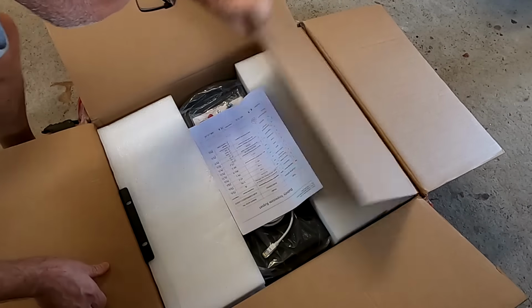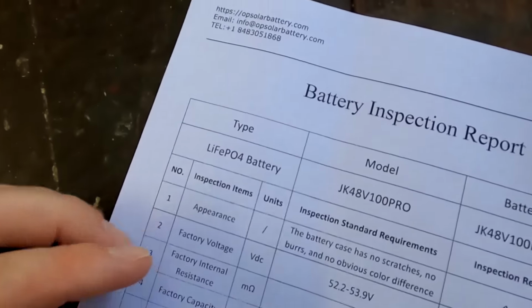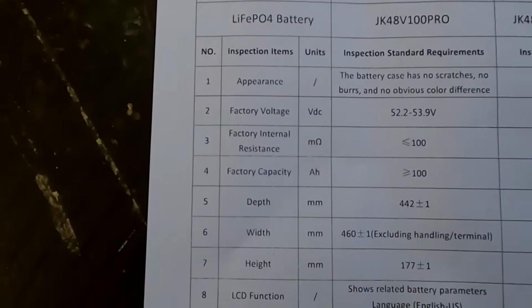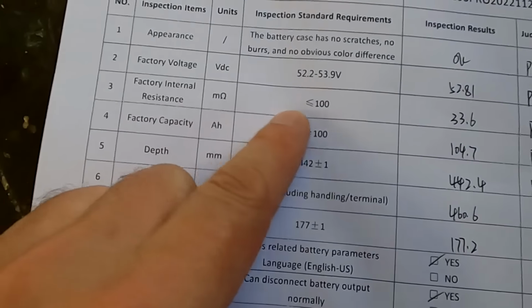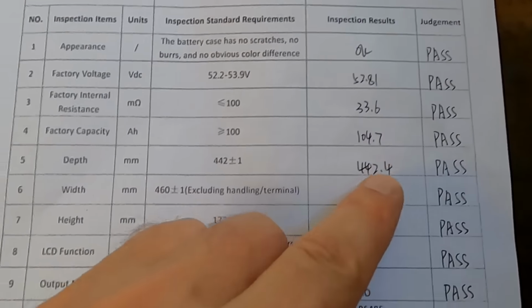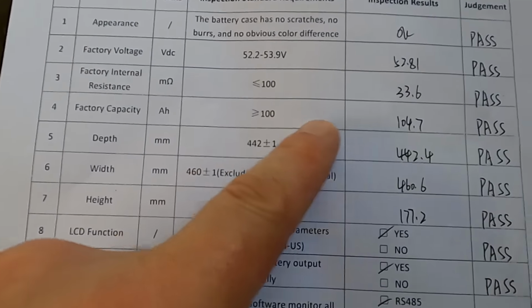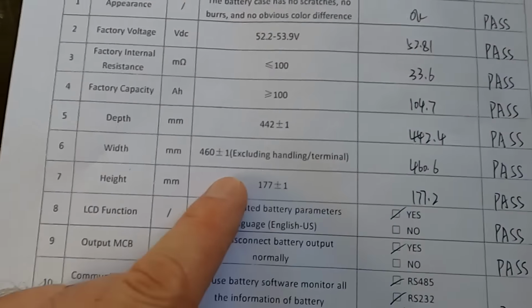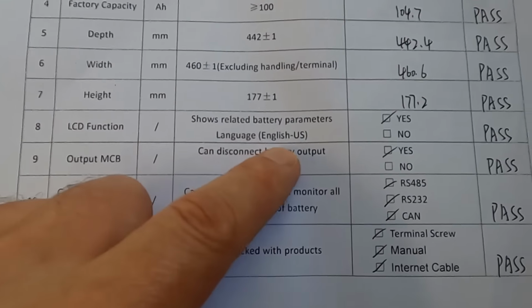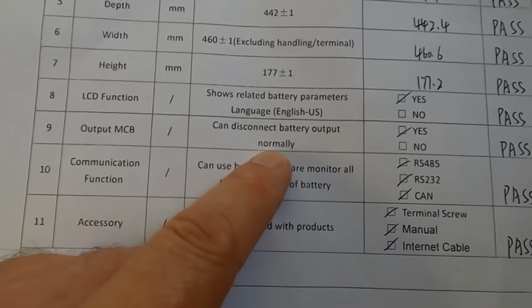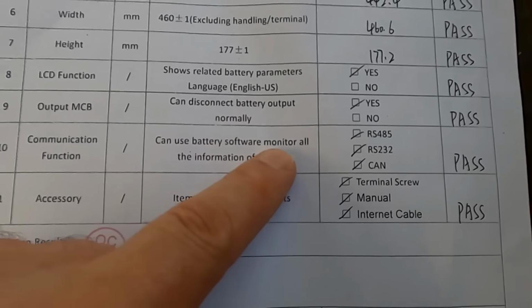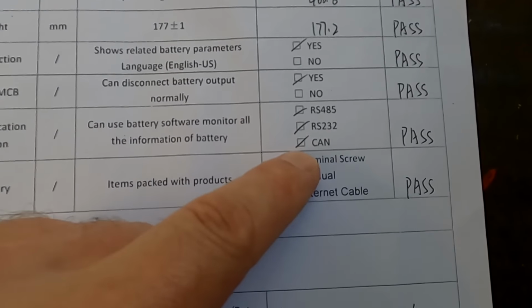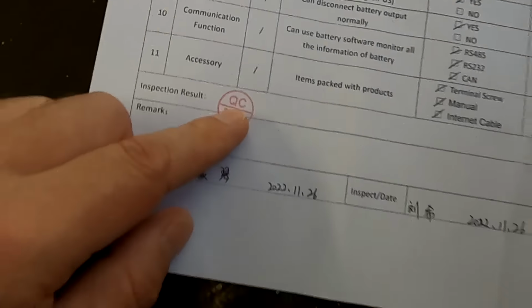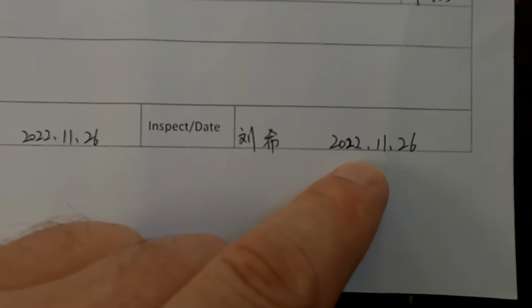Ooh, double box. Oh, that is interesting. Look at this, there's a battery inspection report in here. This is a test report. Internal resistance 33.6, capacity larger than 100 ampere hour, 104.7. Shows related battery parameters, language English, pass. Can disconnect battery output normally? Yes, pass. Can use battery software monitor, RS485, RS232, CAN, pass. QC passed. And this was end of November last year.